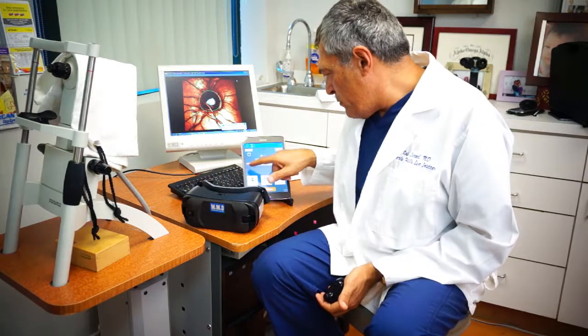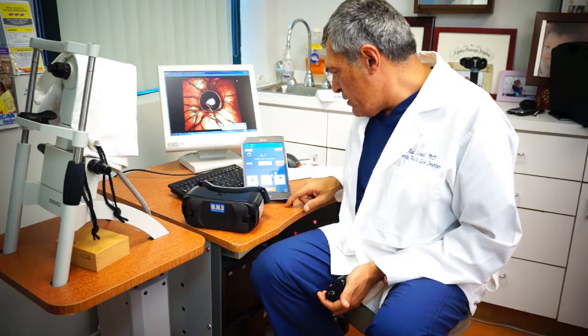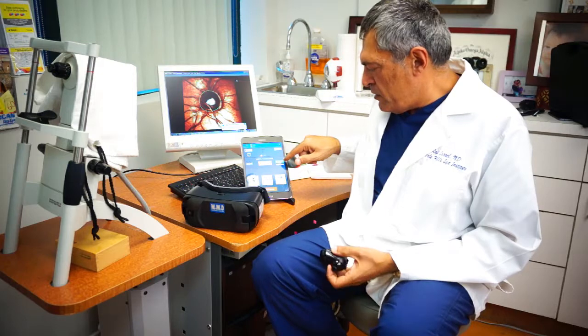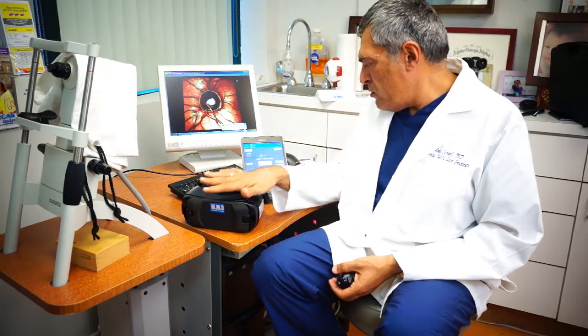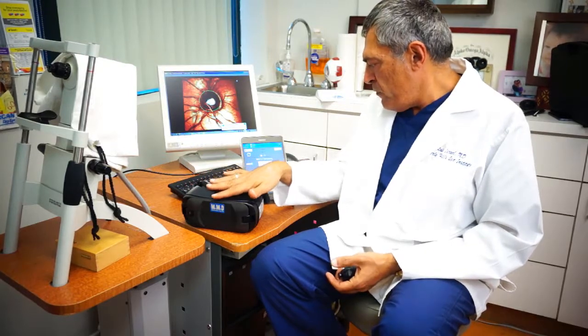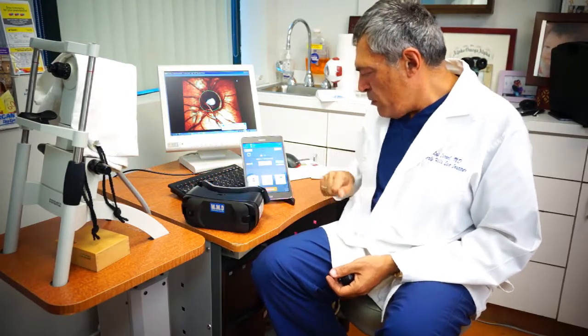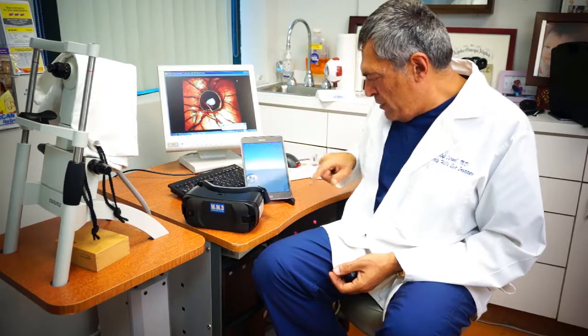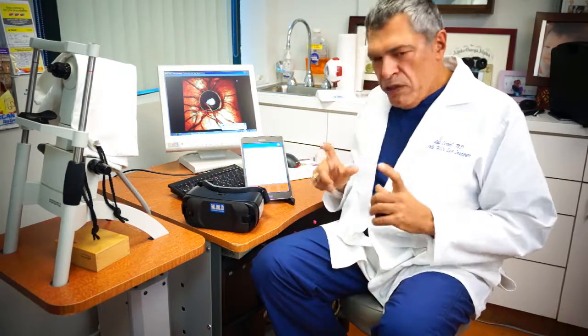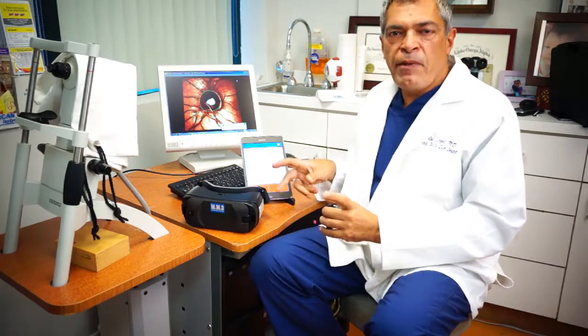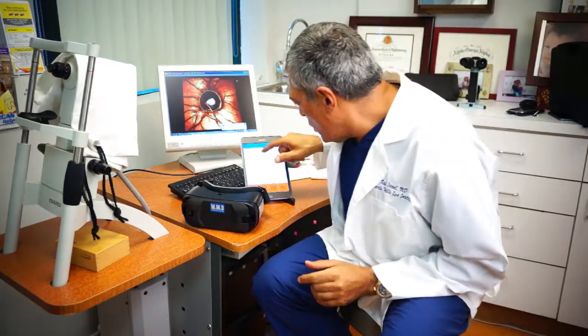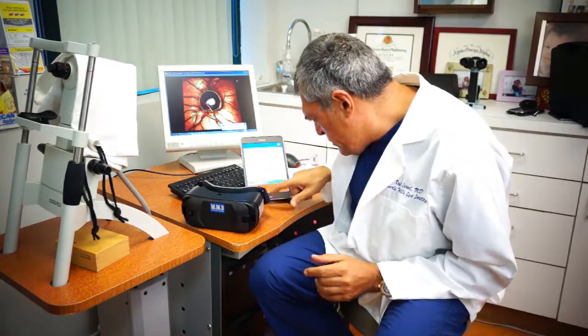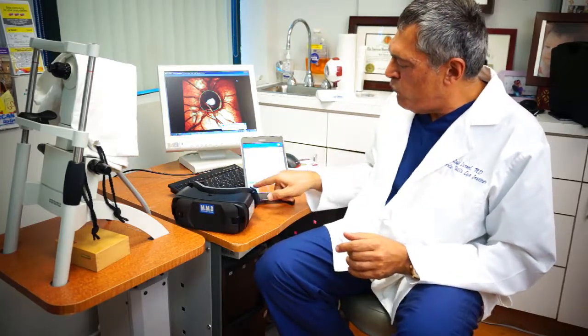Okay, at this point I will turn on my visual field analyzer. So when the green light comes on, it means that the controller is connected now to the goggle, the visual field analyzer goggle. So all you have to do is start the test. There is no need to occlude one eye or another eye as the machine will automatically do this for the patient as they're doing the test. So you just select the patient that you have selected. You select the visual field.